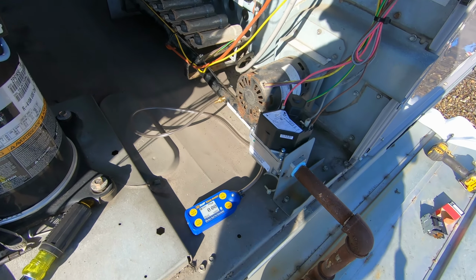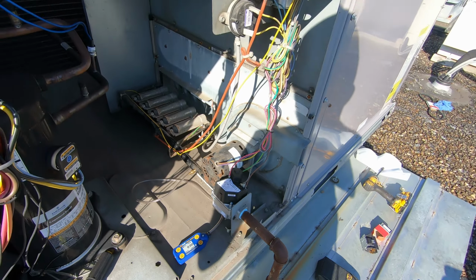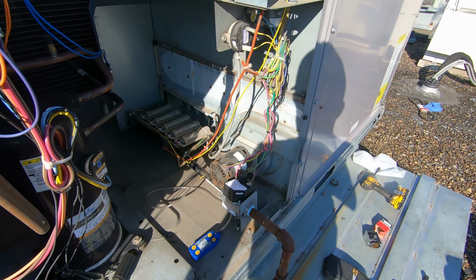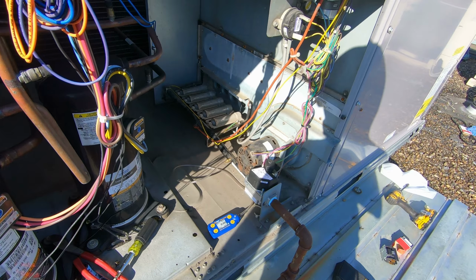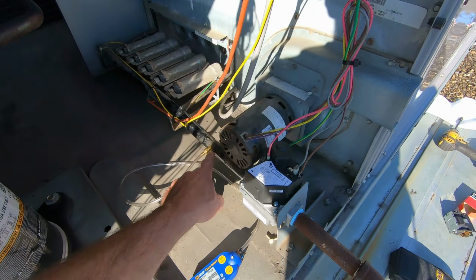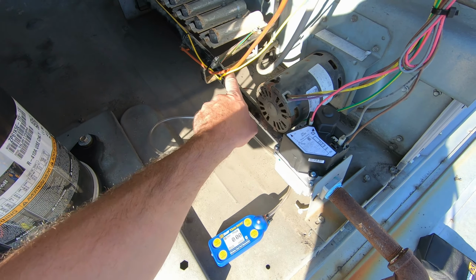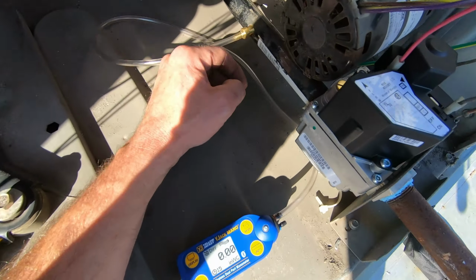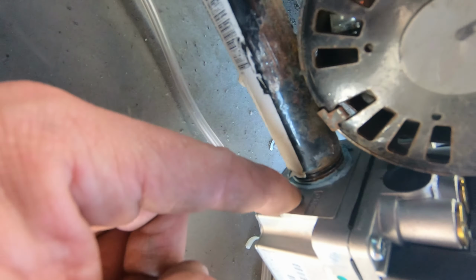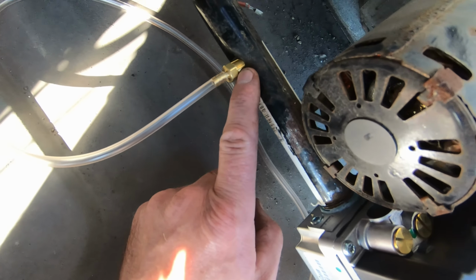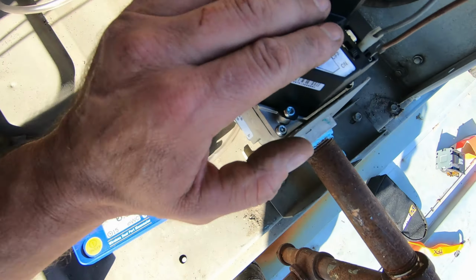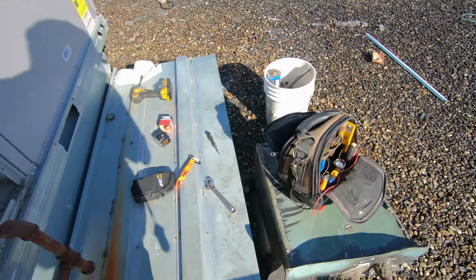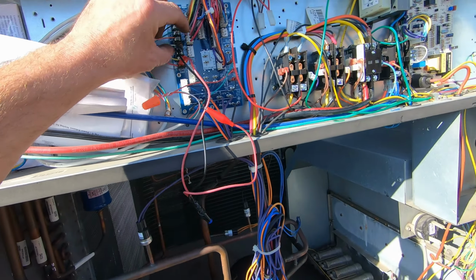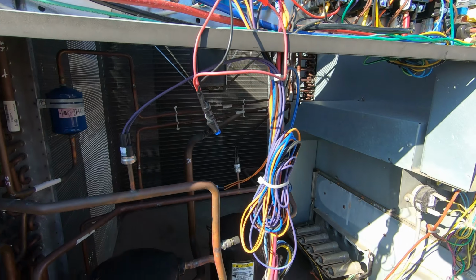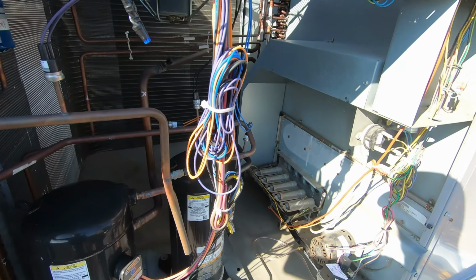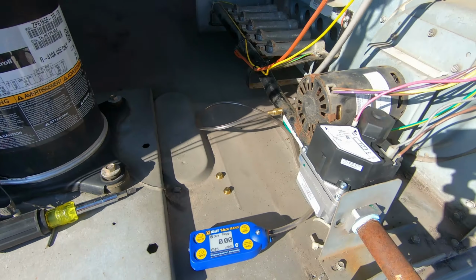I've been primarily using it for checking gas pressures when replacing heat exchangers and gas valves and getting my pressure set correctly. So I'm all hooked up. I just used the test port here in the pipe for the manifold instead of trying to get all the way back here and accessing this one. This one's pretty easy. So I'll wire back up. Gas valve is on, gas cock is on.